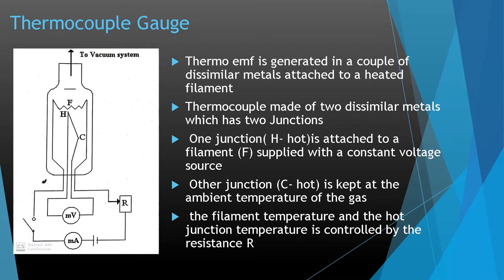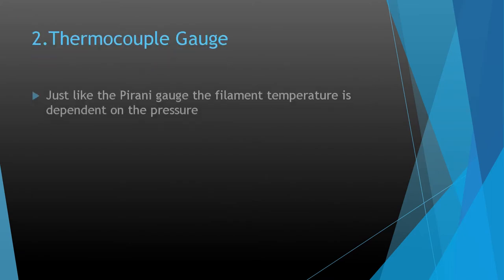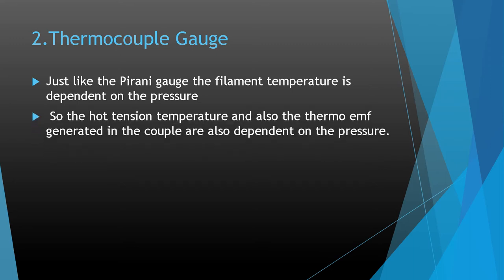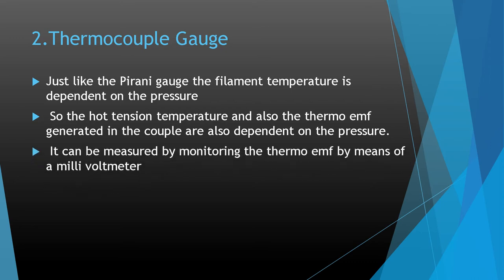A millivoltmeter and ammeter are connected to measure the voltage and current respectively, and the whole system is connected to a vacuum system. Just like the Pirani gauge, the filament temperature is dependent on the pressure. Therefore, the hot junction temperature and the thermoEMF generated in the couple are also dependent on the pressure. This thermoEMF can be measured by monitoring it with a millivoltmeter.